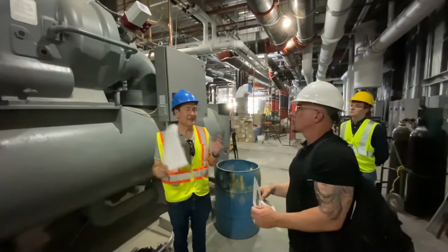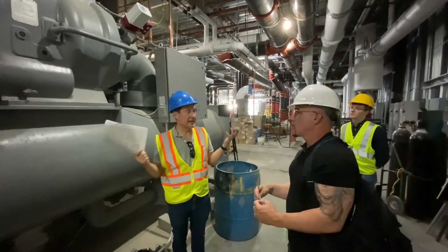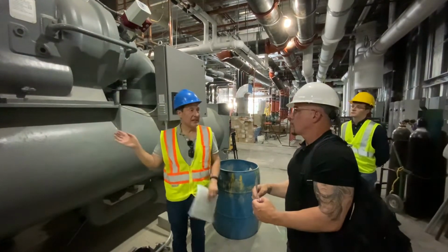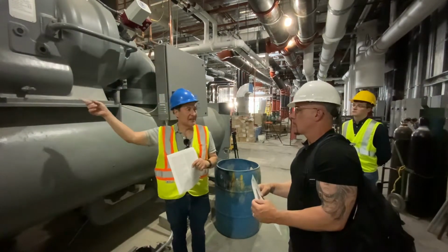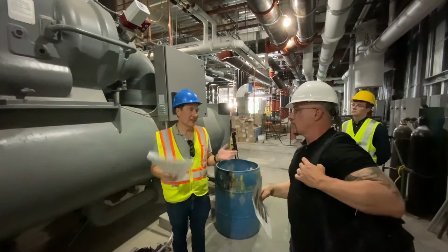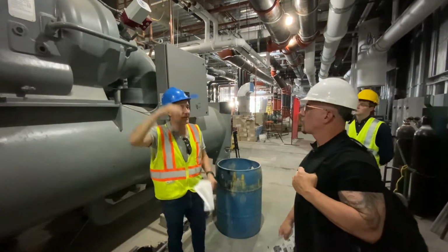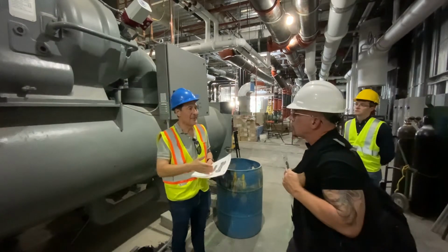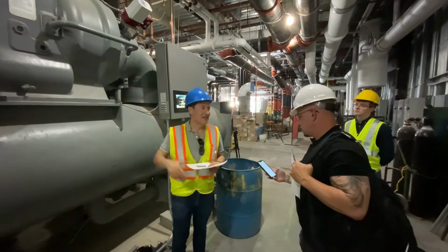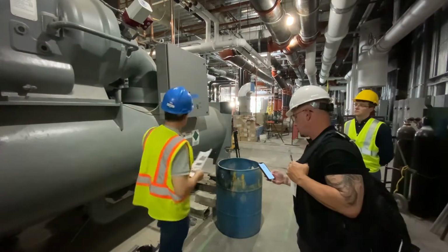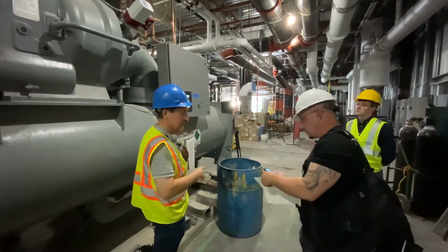Okay. So one thing about VFDs I try to get across to everybody, because there's a misunderstanding in the industry, is that the machine controls capacity based on the speed of the VFD. That's not really how they work. The reason you have inlet guide vanes is because the inlet guide vanes control the capacity of the machine to maintain your set point, whatever that be, 42. The purpose of the VFD is to respond whenever the lift, the pressure differential between the condenser and the cooler, starts to drop.